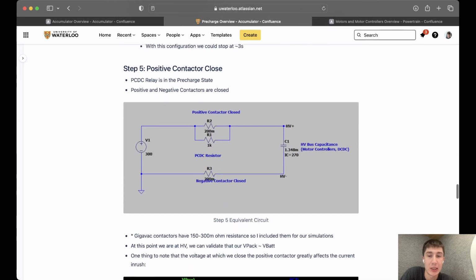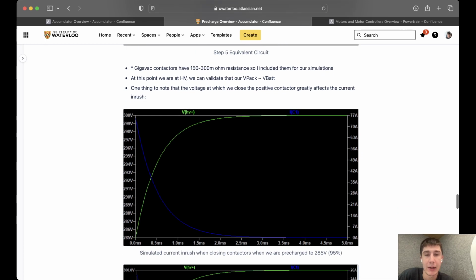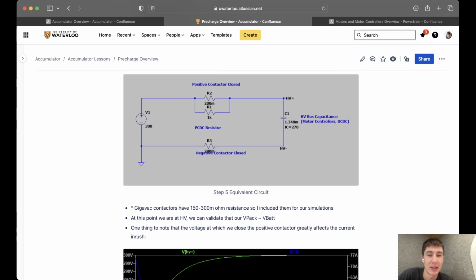So the final step here, which is maybe a little bit confusing, but I'll go over it. We close both contactors. So when we close both contactors, effectively what we do is we're adding 200 milliohms, or effectively 0 ohms, in these two positions. So we're closing the circuit, and now this 1 kilo ohm resistor is effectively useless, and we just have a solid path across our capacitor. This is going to induce a little bit of inrush current because we're removing this 1 kilo ohm resistor, and our capacitors are technically never fully charged, but it's a very small amount of impulse current.